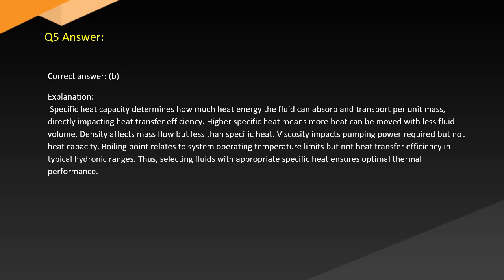Answer. Correct answer, B. Explanation. Specific heat capacity determines how much heat energy the fluid can absorb and transport per unit mass, directly impacting heat transfer efficiency. Higher specific heat means more heat can be moved with less fluid volume. Density affects mass flow, but less than specific heat. Viscosity impacts pumping power required, but not heat capacity. Boiling point relates to system operating temperature limits, but not heat transfer efficiency in typical hydronic ranges. Thus, selecting fluids with appropriate specific heat ensures optimal thermal performance.